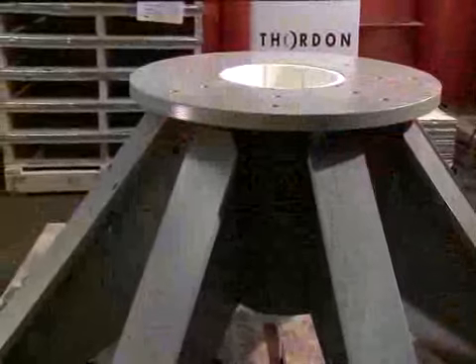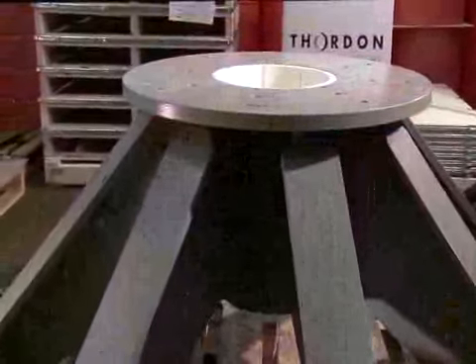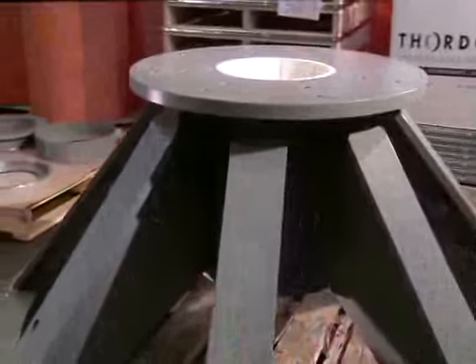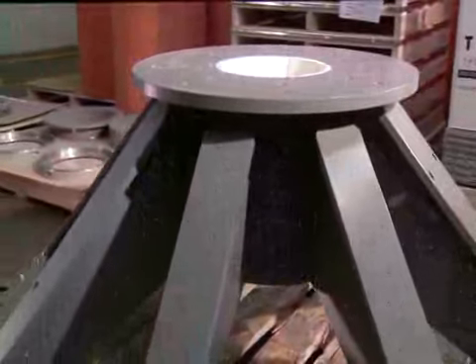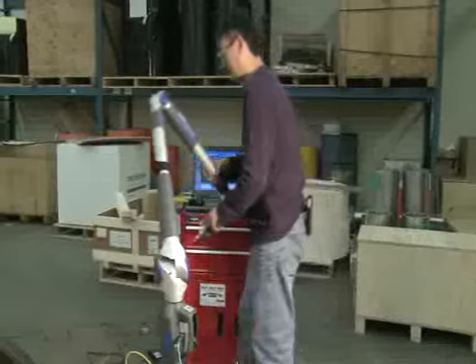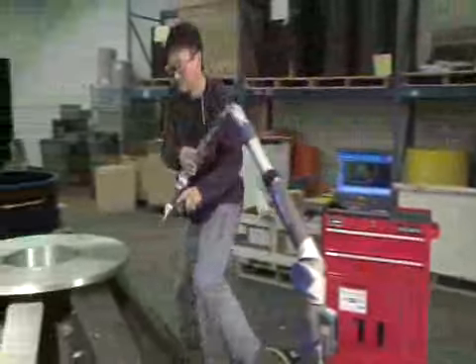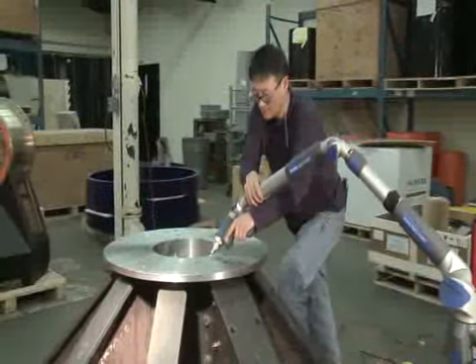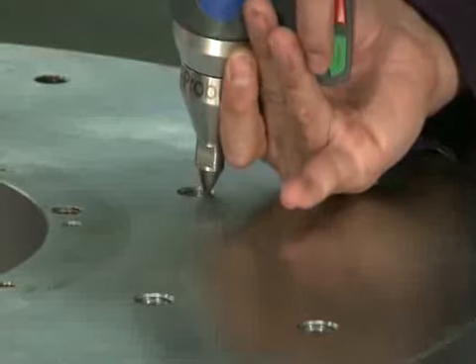This newly designed and fabricated steel lower bearing carrier will fit exactly into place above the existing turbine head cover, thus replacing the original cast iron and white metal bearing. For several reasons, it's usually better to start from scratch than to attempt to modify and reuse a 100-year-old casting.